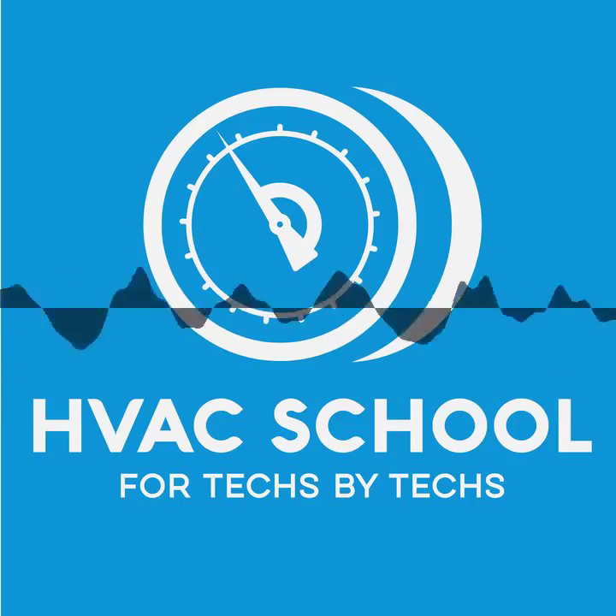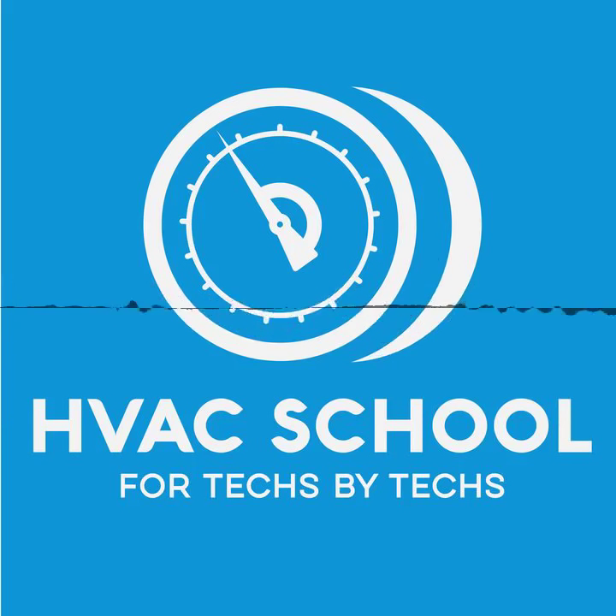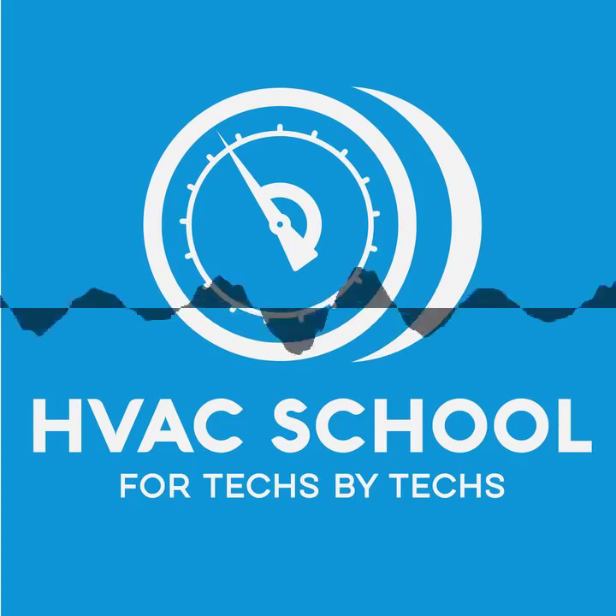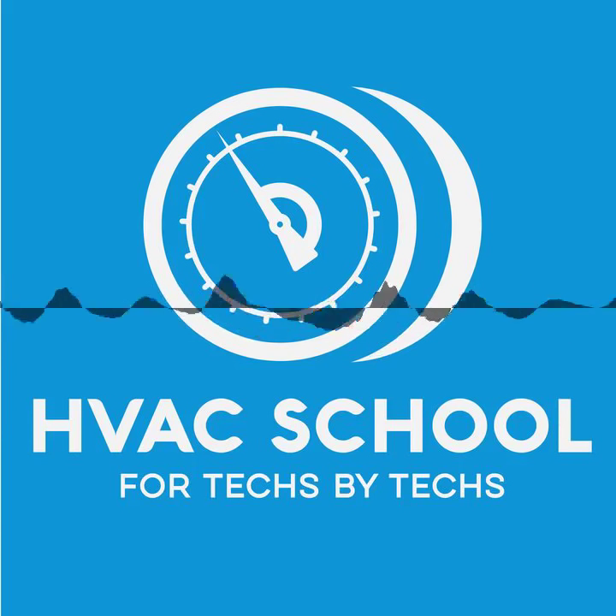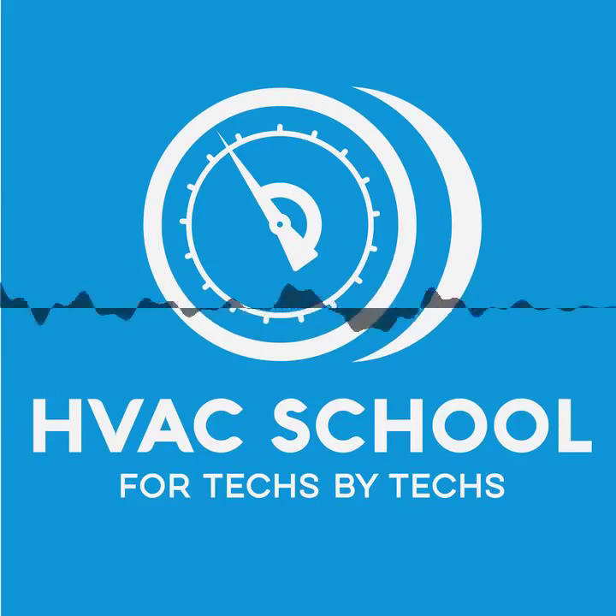You always use dry nitrogen. And again, pressure test to the manufacturer's specifications. Pressure tests can vary from anywhere from 250 to about 600 pounds, depending on the application. Make sure you follow the manufacturer's instructions. Remember that in heat pumps, the pressures can easily get up to 650, 700 pounds under normal operation, and of course, much higher in an overcharged system.